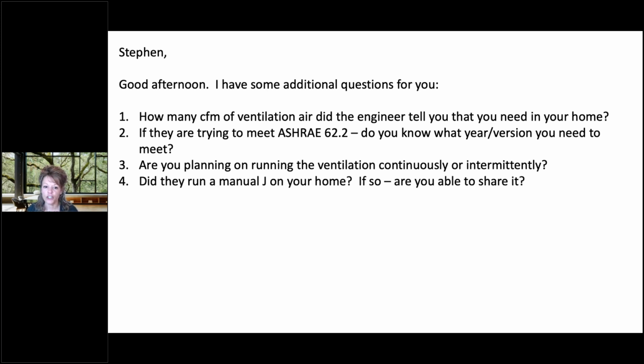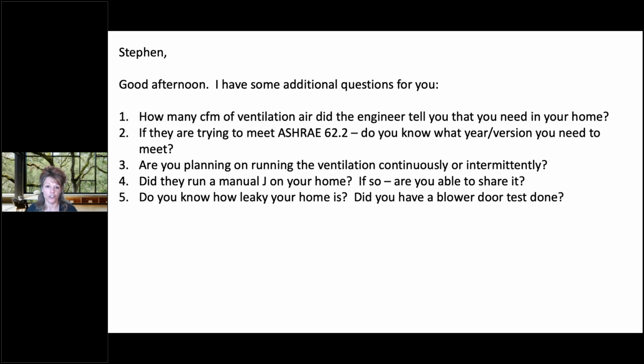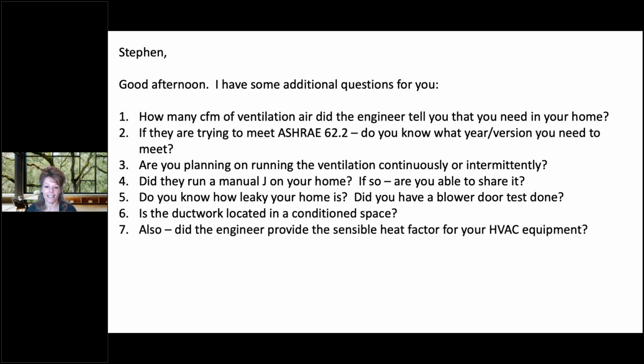Is there a Manual J done on the home? That helps us a lot to understand the latent loads they're trying to deal with in that home. Do they know how leaky their house is? Was a blower door test done? Where's the ductwork located? And did the engineer provide the sensible heat factor for their HVAC equipment? We need to know, when the AC is running, how much we can count on that AC system to remove moisture, because we are a supplemental dehumidification system.